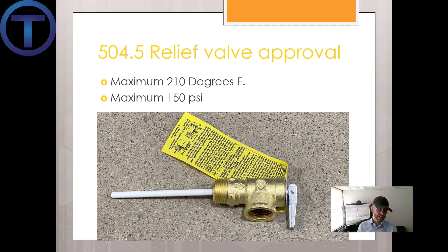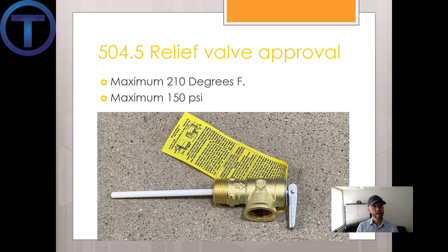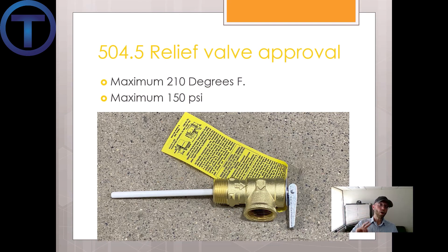504.5 states that a temperature pressure relief valve shall bear the label of the approved agency. There's that label that's always hanging on there — leave it, it's supposed to be there. It should also have a maximum temperature of 210 degrees Fahrenheit — only two degrees below the boiling point of 212 — and a maximum of 150 PSI.